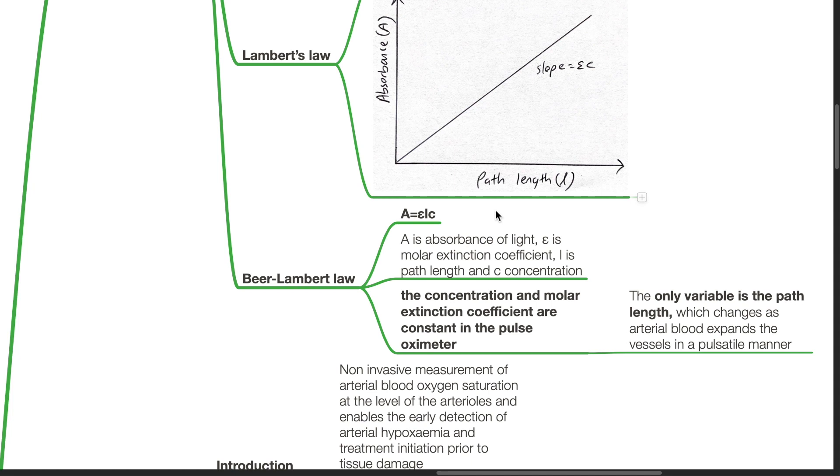The concentration and molar extinction coefficient are constant in the pulse oximeter, and the only variable is the path length, which changes as arterial blood expands the vessel in a pulsatile manner.